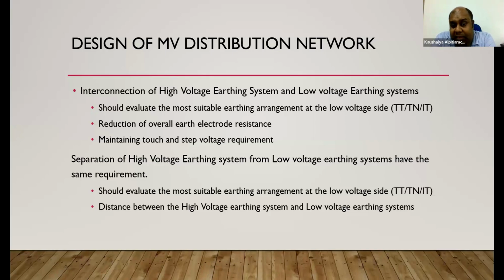Separation of high voltage earthing system from low voltage earthing systems has the same requirement, but it's not that crucial for reducing your overall earth electrode resistance. But some other factors may dominate the reduction of overall earth electrode resistance. So you should evaluate the earthing arrangement and the distance between the high voltage earthing system and your low voltage earthing systems.